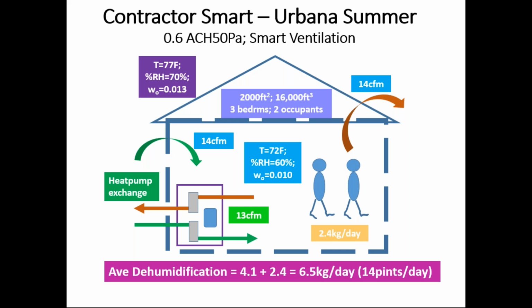So this 13 CFM is a little deceptive because that's a 24-hour average. But if you had 10 people in there for just an hour or two, the ventilation rate might go up to 200 or 300 CFM for that period of time. And then people leave, and then it ramps back down. And so while you're seeing what looks like a very low level of ventilation, it in actuality is not.